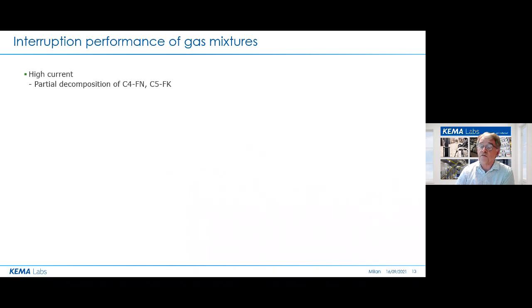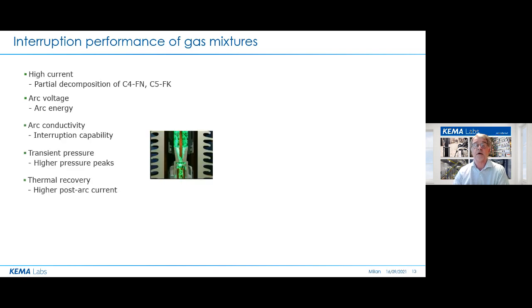Well, next, of course, in line is the current interruption. We see that in many parts during the interruption process, the new gases show different features. First of all, one of the features is the voltage of the arc. During the high current phase, there is some partial decomposition of C4-FN, C5-FK. We will come back to that point soon. Then during the arc, there is an arc voltage, so the arc energy is different in the new gases. But also speaking about the interruption itself, the interruption capability depends on the decay of arc conductivity in the last phase of existence of the arc.